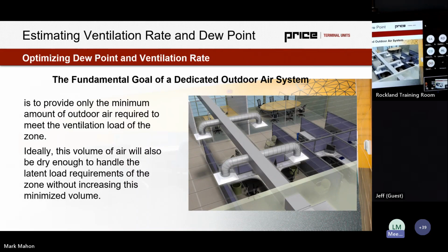Of course, we often have to. Sometimes we need that higher volume of dry air to actually offset the latent load of the zone, but ideally, we can do it with the same volume. And I just wanted to talk a little bit about what that process would actually look like from a design perspective.